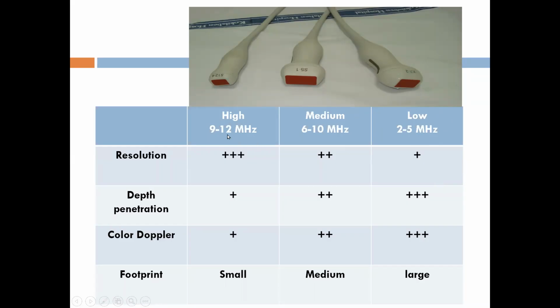Because the frequency is high, the penetration power is less, so the depth penetration is less with the high frequency. The medium will have medium depth penetration, and the low frequency probe will have the highest penetration. Even for color Doppler, we prefer a low frequency probe. It will give the maximum color output. The high frequency probe will have a smaller footprint. The medium frequency will have medium and the low frequency will have a larger footprint.